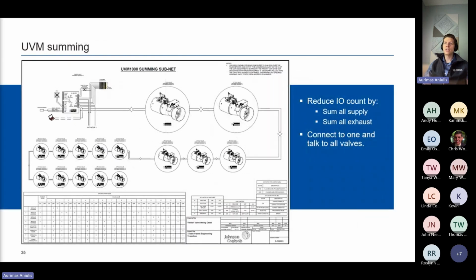Another great thing about the UVM is that if you daisy chain all of these on our RS-485 pseudo Modbus standalone network, you can get up to 15 valves to sum their CFMs into a single master CFM. This is very valuable when you have a room with 15 air valves and you're running out of IOs on the room level controls. Here I can take my total exhaust and my total supply, and I just have two sets of IOs now to take my total supply, total exhaust, and balance the room. Neat little feature. And when you wire them daisy chain, you only need to connect to one so that you can then command and control any other ones through this daisy chain setup.